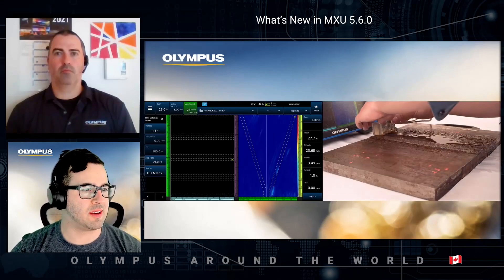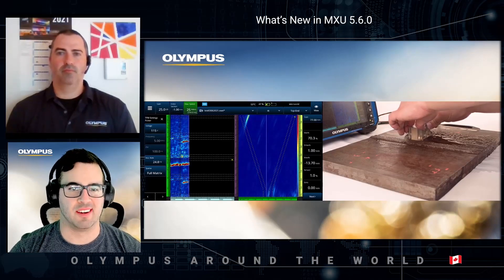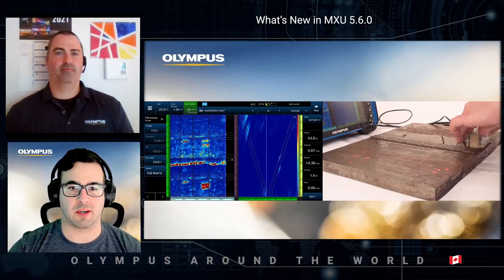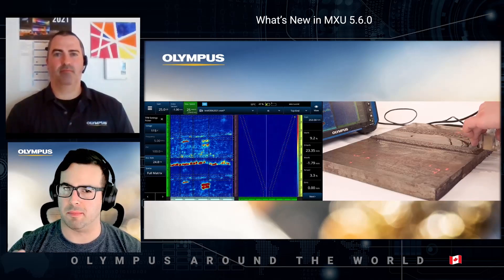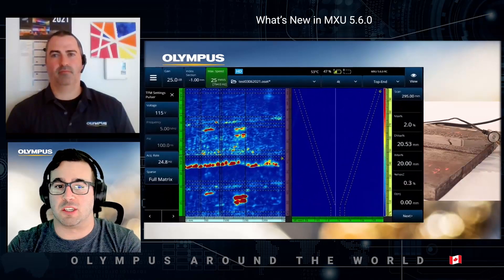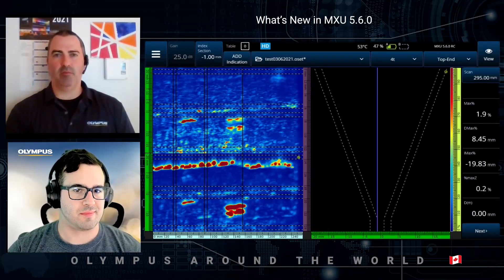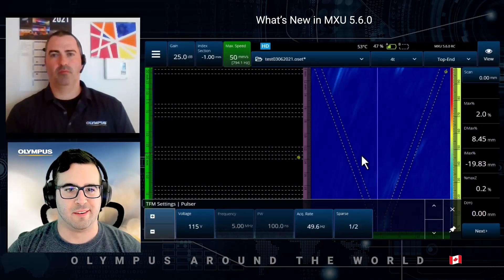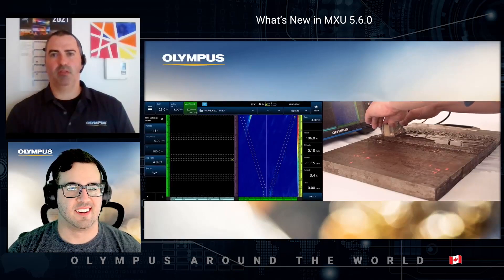On the left you can see the screen of the OmniScan X3 and on the right my hand scanning the plate. There is a black bar on the screen, meaning no data was acquired because I was moving a bit too fast. Once I scanned the part more slowly, you can see the result. At full matrix, you are limited to 25 millimeters per second. Now I'll switch the matrix to one-on-two, which increases the acquisition rate — basically doubling it.